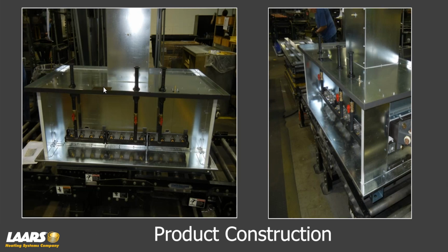What they're building is probably a 500,000 or a 750, could be even a 1 million. It's got a single blower. And so you're going to blow air pressure down into this chamber. There'll be a cover door that goes over this. So you want to make sure this chamber is tight, and that's why even the chamber is gasketed. Okay? So we have the upper deck, and then they also add the flue collection. The flue collector is where all your flue gases come into and then out your breeching.